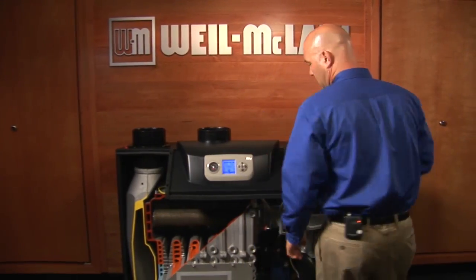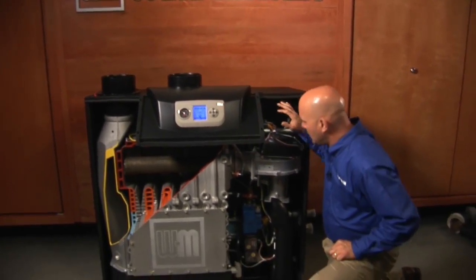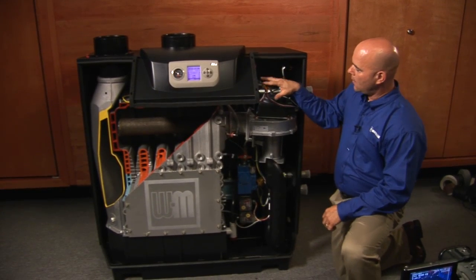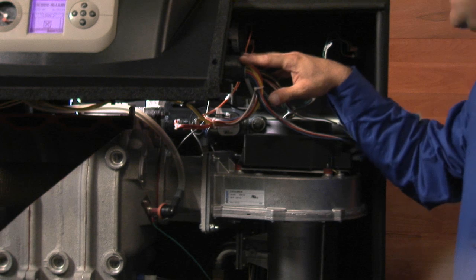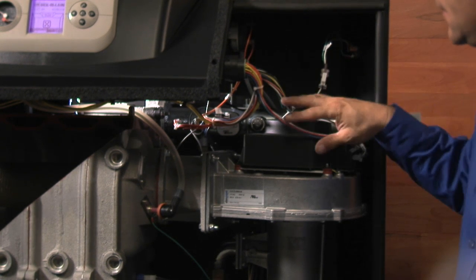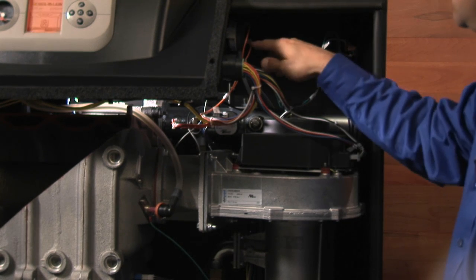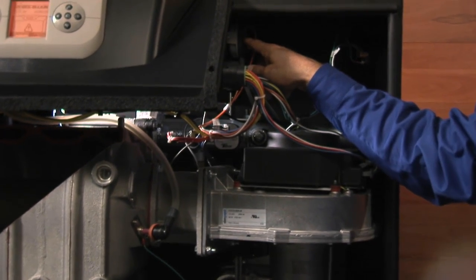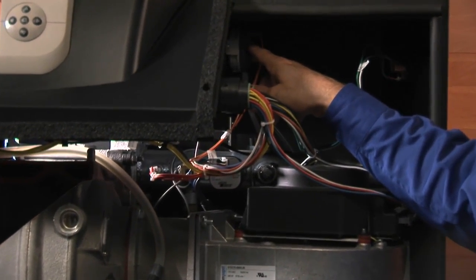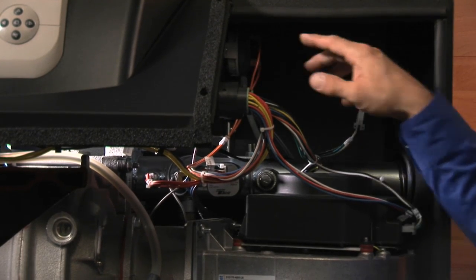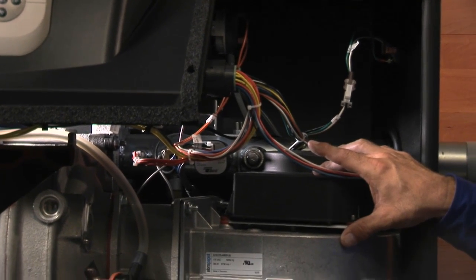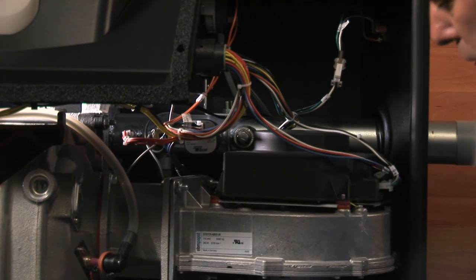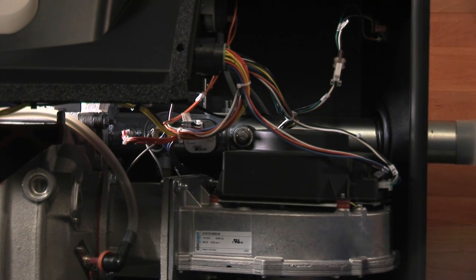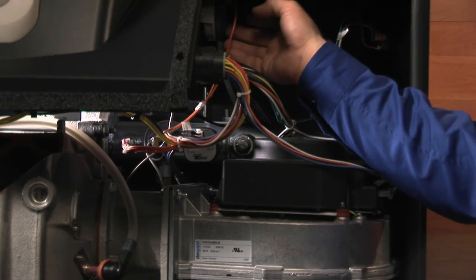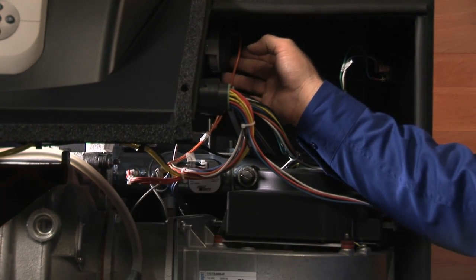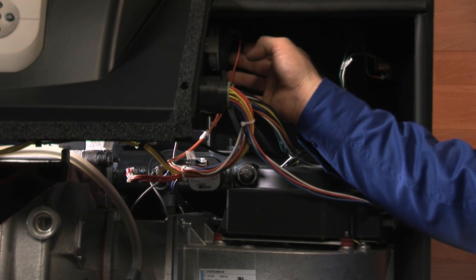We swing around to the right side of the boiler, and over here we have our wire transitions from the control compartment down into the heat exchanger compartment. We have a pressure switch, an air pressure proving switch. The reason for the pressure switch on the commercial boiler is we have a very large fan, and we need to make sure that we don't blow the condensate out of the condensate trap. So we're monitoring the airflow across the heat exchanger with this pressure switch.